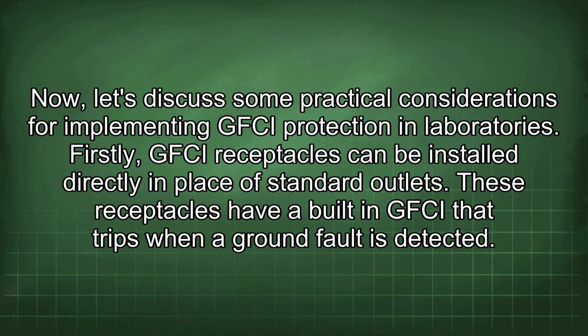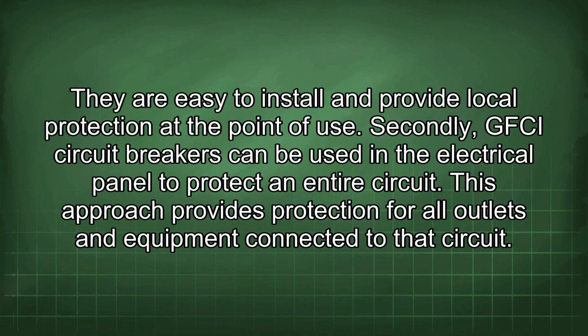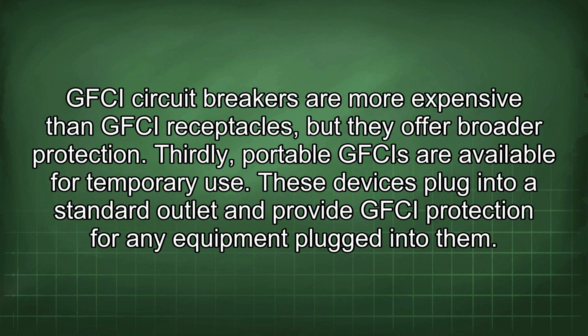Now let's discuss some practical considerations for implementing GFCI protection in laboratories. Firstly, GFCI receptacles can be installed directly in place of standard outlets. These receptacles have a built-in GFCI that trips when a ground fault is detected. They are easy to install and provide local protection at the point of use. Secondly, GFCI circuit breakers can be used in the electrical panel to protect an entire circuit. This approach provides protection for all outlets and equipment connected to that circuit. GFCI circuit breakers are more expensive than GFCI receptacles, but they offer broader protection. Thirdly, portable GFCIs are available for temporary use.